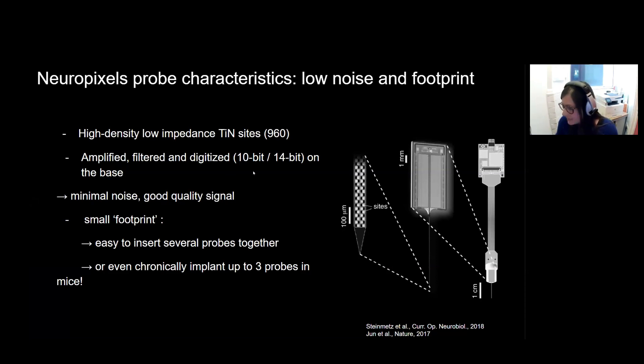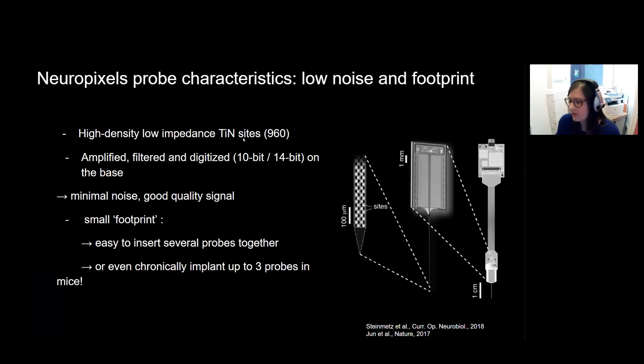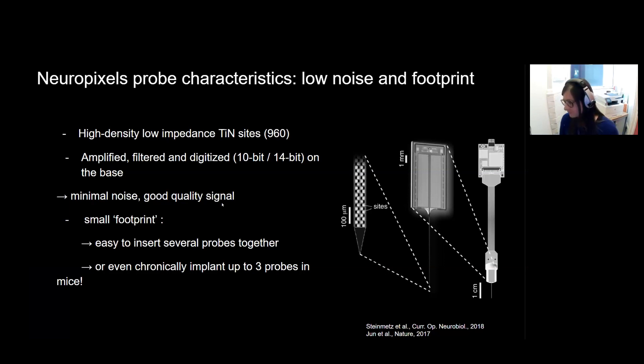Additionally, all of the sites in the Neuropixels are high density, low impedance sites. All the data is amplified, filtered, and digitized on the base. So you have a 10-bit digitizer for the 1.0 probes and a 14-bit digitizer for the 2.0s. And this means that you have minimal noise and a really good quality signal.